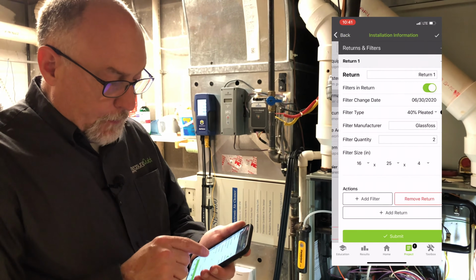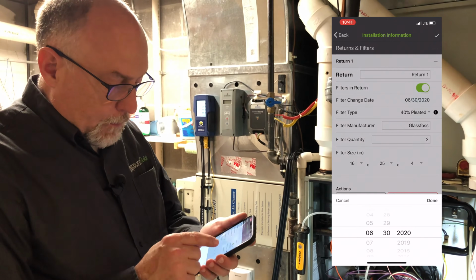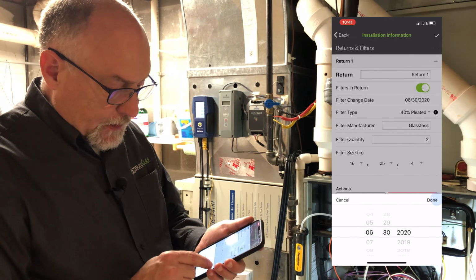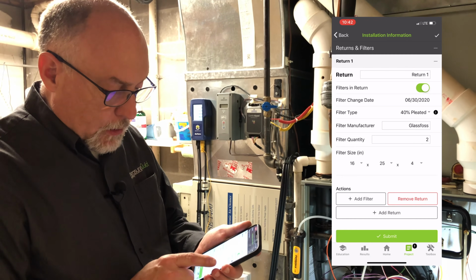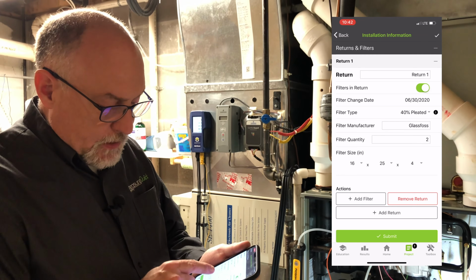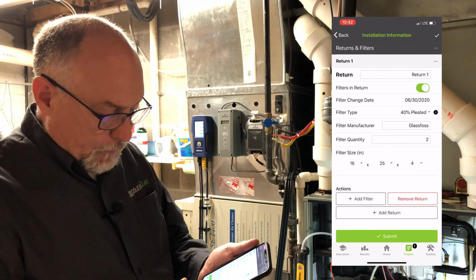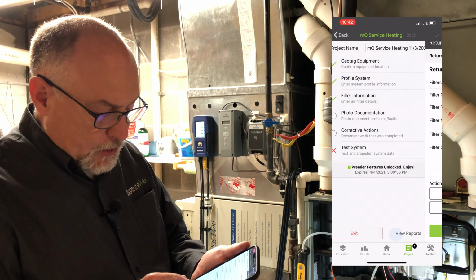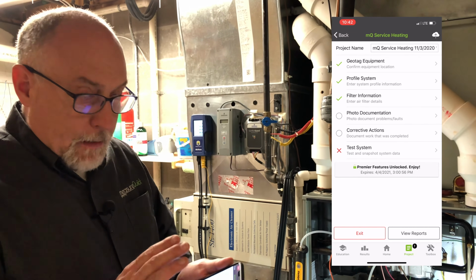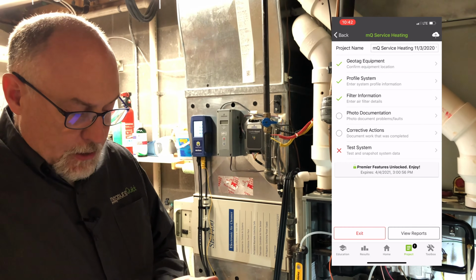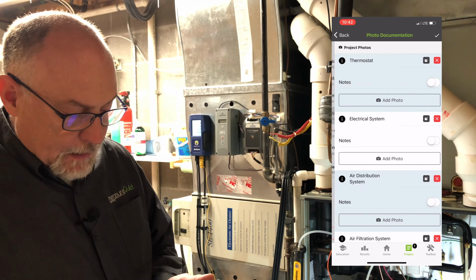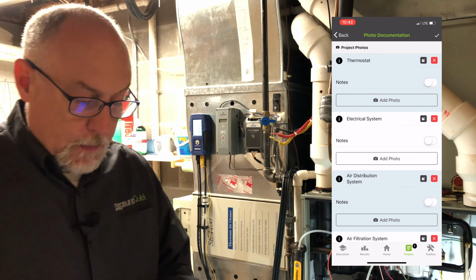And our filter information, the last time I changed the filters was 6/30/2020, so that's still good. I'm going to leave that there. I have two 16 by 25 by 4s, 40% pleated filters. I'll hit submit. And you guys saw me inspect those earlier. And now we get into the photo documentation section. This is where we would document a couple things here. So I'm going to go ahead and sneak past you here. And let me get a level here.